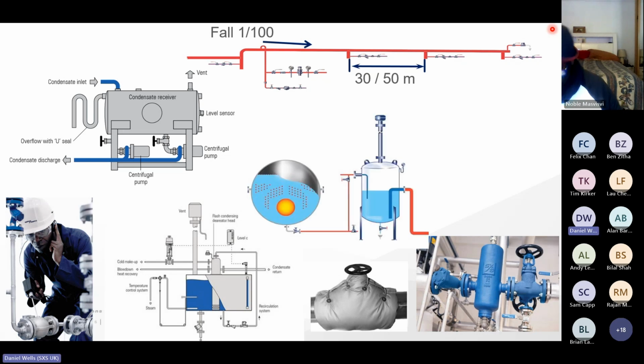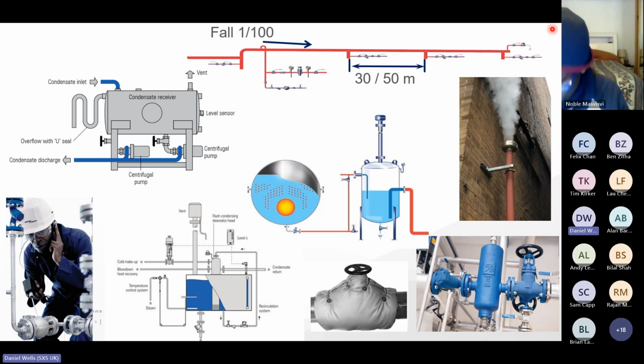Boiler controls. We want to ensure that we're putting the bare minimum of hot water to waste in order to maintain the water chemistry. But most importantly of all, we need to keep an eye on those vents. Those vents give us an indication that we may have a number of failed steam traps. We may have a number of failed condensate pumps, and we're simply losing steam and also condensate. So there's a significant financial inefficiency if those vents are left unaddressed for any reason.